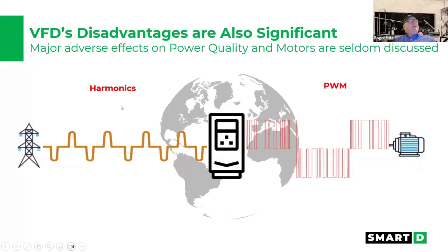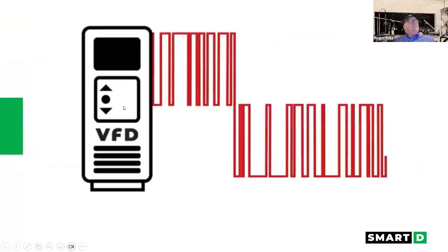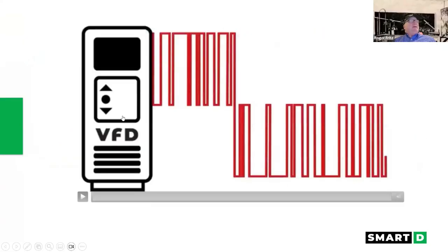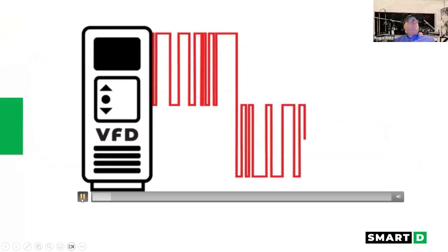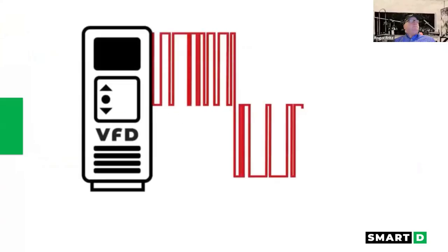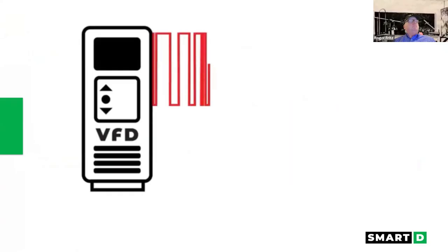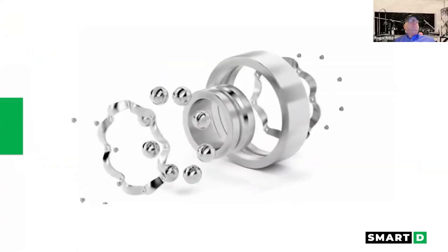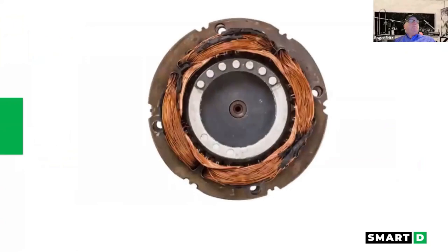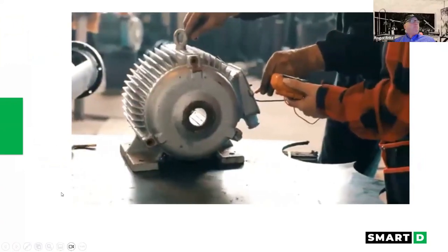issues. But when you get harmonics into the load, this is a little video I'll show you. Sine waves generated by pulse width modulation. This PWM signal has multiple drawbacks. PWM creates currents that are destructive to the bearings and insulation, resulting in the premature aging of the motor.